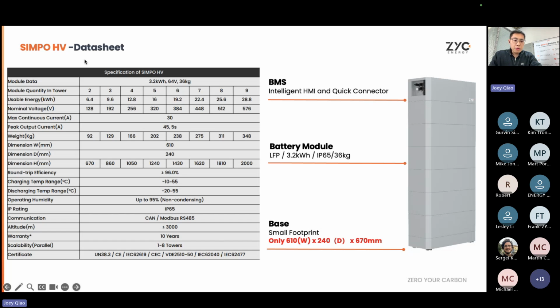Each one is 3.2 and 36 kilos, so it's not heavy. I think at least 1 or 2 people can install and handle it. For one stack, because the series connection gets a high voltage, we have a minimum number requirement. I don't think it's an option for you now, but the minimum is 2 battery modules, 6.4 kilowatt hour, and the maximum is 9 modules, giving you 28.8 kilowatt hour usable.